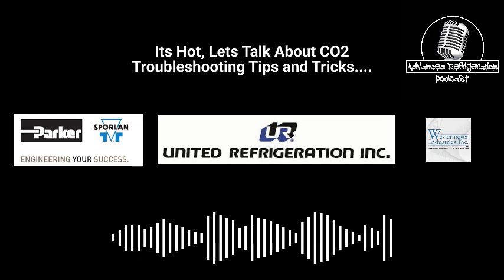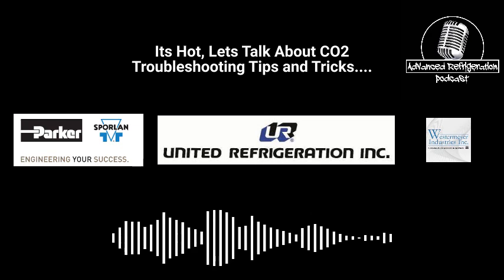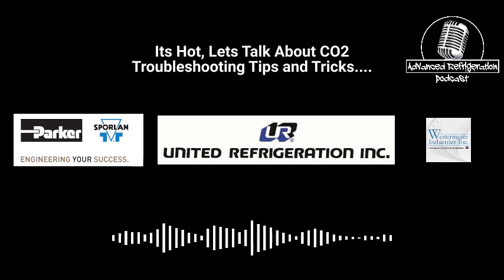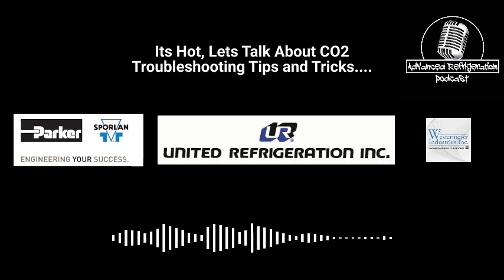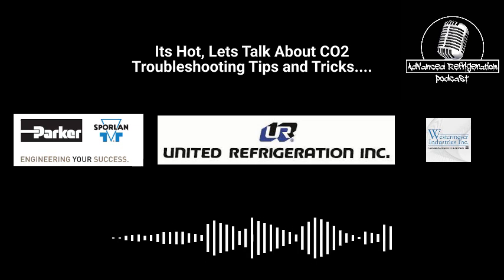So the Zero Zone racks, they have a hot gas injection valve in there. I don't know if the port's bigger or what, but it will overload the compressors if you leave it on. It's got enough to superheat and keep the load up, that's for sure. I'd rather have that than the smaller ones. Some of them are made just for increase in superheat, and some are made for increase of superheat and/or keeping the load up in case the load drops off. So everybody I've seen has tried to do both with it.